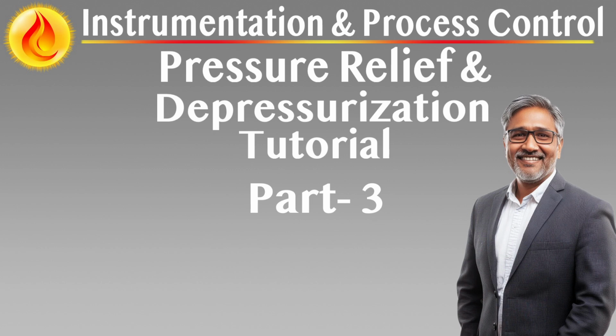Discharge back to process or storage. Where feasible, some relief streams may be safely routed to lower pressure process equipment or storage vessels instead of the flare. This is viable only if the discharge will not cause overpressure or overfilling of the receiving system. The flow does not conflict with normal operations or create hazardous conditions. No reverse flow or relief valve leakage occurs due to low back pressure in the receiving system. Back pressure assumptions must be conservative, and interactions with other relief devices must be validated.